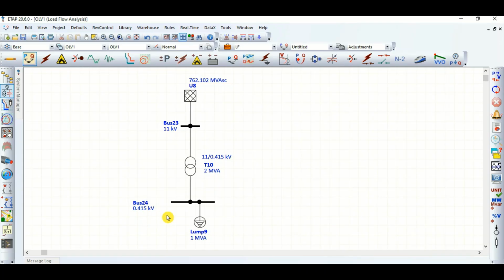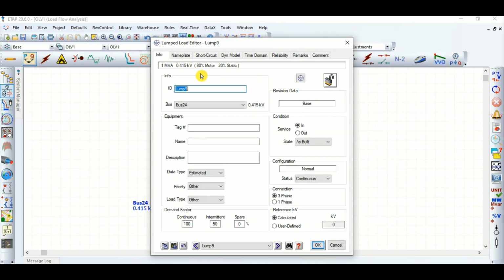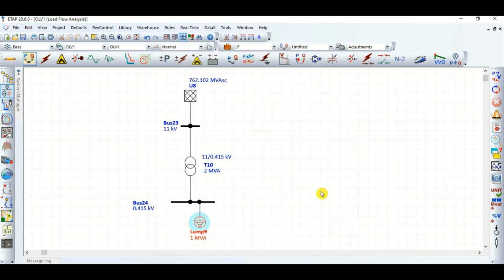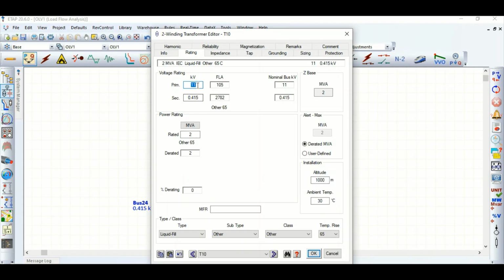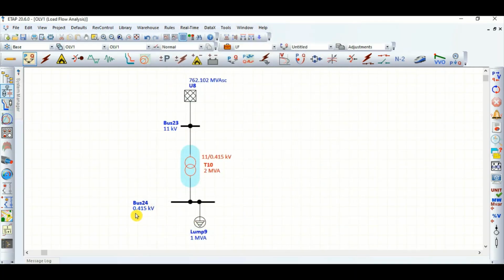And in the LV system, the 415 volt system, I have connected a 1 MVA load, 80% motor and 20% static load. So we will see some case studies. What is the impact of this transformer voltage ratio, primary side voltage, secondary side voltage? Sometimes you will see in the transformer data sheet that it is 11 kV per 0.433 kV, whereas the bus is 0.415 kV. So what will be the impact? If we consider this transformer secondary side as 415 volt, and again if we consider the transformer no load voltage as 433 volt, what will be the impact with respect to load flow and short circuit studies?